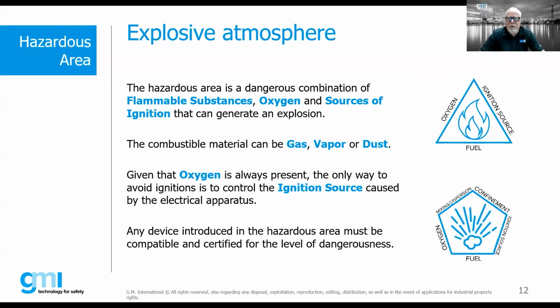So obviously, when we're talking about intrinsic safety and the benefit of one particular type of barrier versus another, let's backtrack just briefly and talk about explosive atmospheres. The concept of intrinsic safety is one that we use as a protection concept for providing electrical instrumentation equipment in a flammable gas or dust environment. A hazardous atmosphere is one in which we're going to have a flammable gas present in combination with oxygen or air.